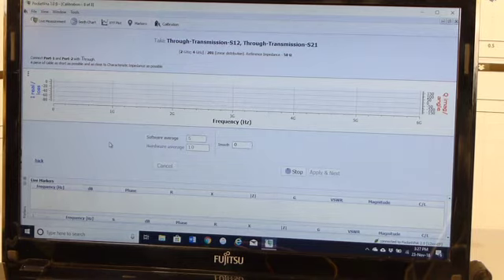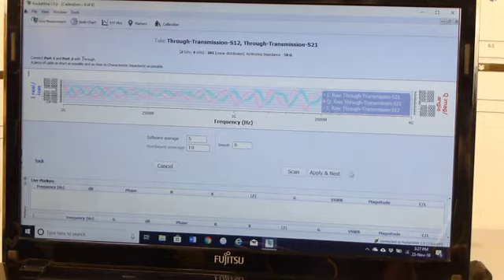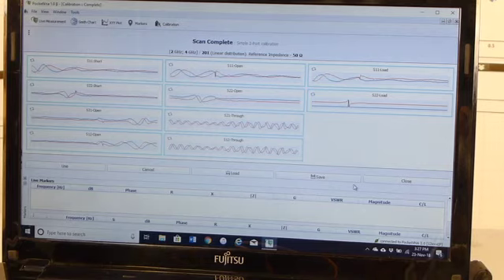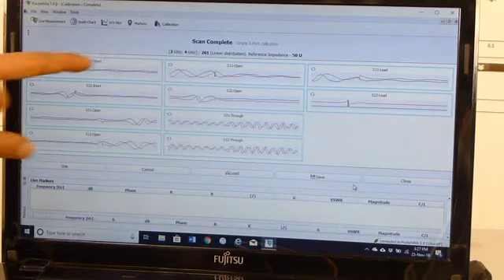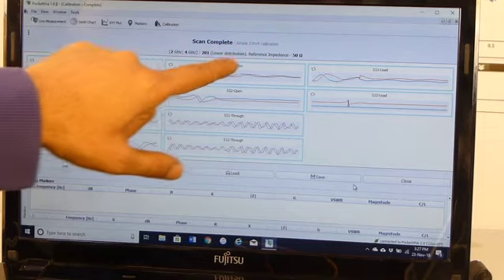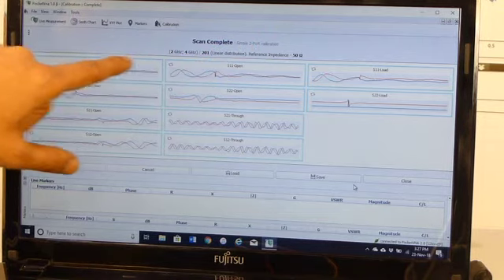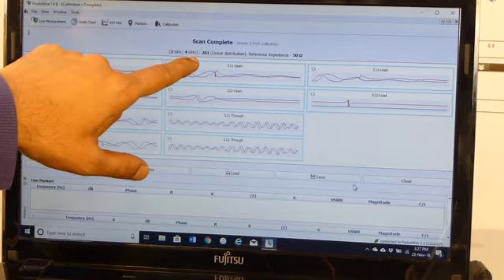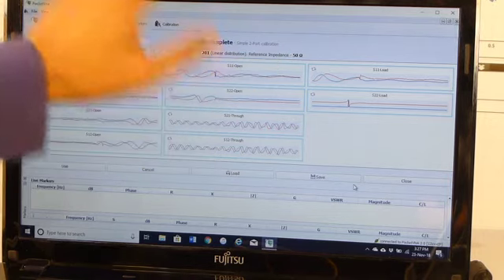Now as you can see, the calibration is almost over. Now it says apply and next. We will press apply and next. Now as you can see, it is showing all the readings here. It says scan complete, simple 2-port calibration. We had selected 2 GHz as the start frequency and 4 GHz as the stop frequency, 201 readings, and the reference impedance remains the same, 50 ohm.